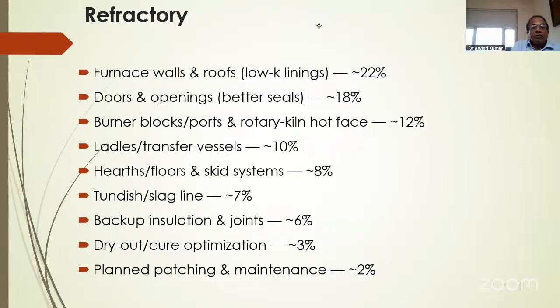Refractory: high temperature resistant materials. It protects furnace and boiler walls, linings, and vessels exposed to extreme temperature. It includes fire clay, high alumina bricks, silica, magnesite, and castable ceramic fibers. It reduces fuel consumption and heat losses, improves the life of equipment, improves efficiency, and lowers operating cost. Furnace walls and roofs reduce 22%, doors and openings 18%, burners and blocks. Different areas have such potential for saving energy.